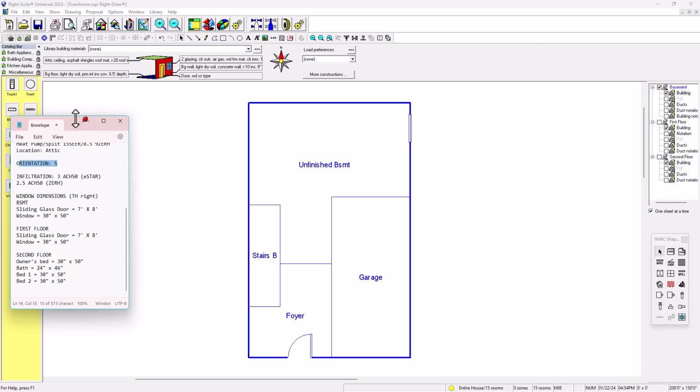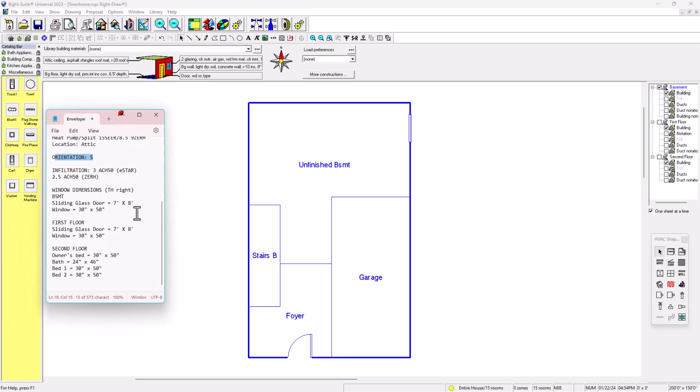However, this is also very important. If you're putting in windows and doors, you need to know the dimensions. Usually the dimensions are already located in the architectural drawings. The architect gives you a windows schedule and doors schedule, so that's where you can find them. Or if it's a site survey, you can measure the windows or the size of the doors. But whenever it's a big building, it's so much, so you can take an approximate window-to-wall ratio of like 40%. But in residential, we usually have the sizes, okay? So in this case, in the basement, the window is 30 inches by 50 inches.